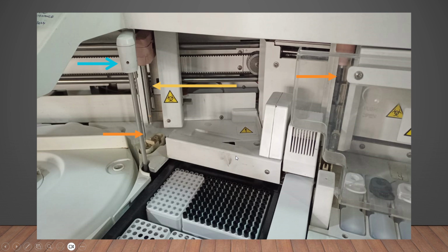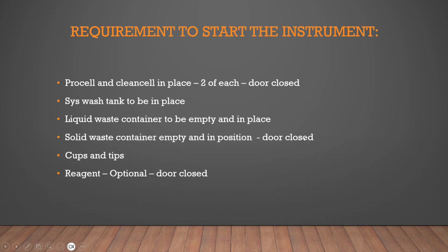Okay, so now if you look at the probes, this yellow mark is the reagent as well as sample probe. The sample is picked up by this probe, as well as the reagent, and this probe uses individual tips to pick it up. Another probe which is present, this one, is the mixer probe. It helps in mixing the beads that are present in the reagent. Only one particular reagent of the three is mixed by this; only the micro beads are mixed by this probe. And this is the sipper probe. It will come this side to pick up the solution from the cups which have already reacted, through which it measures the values.